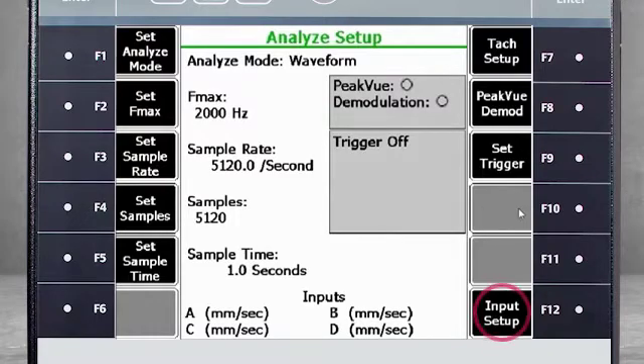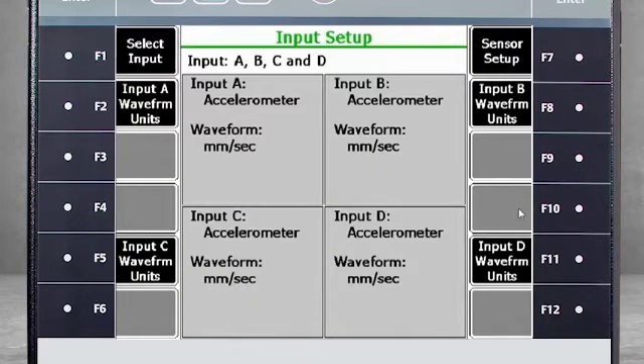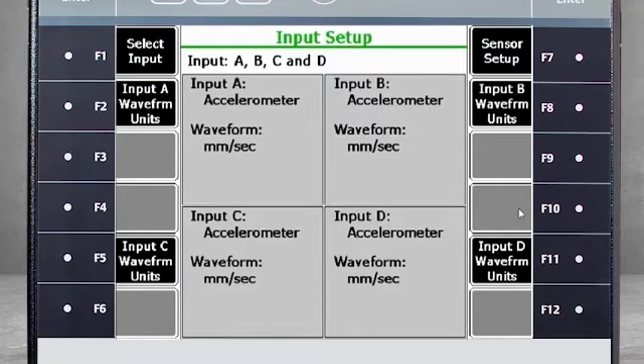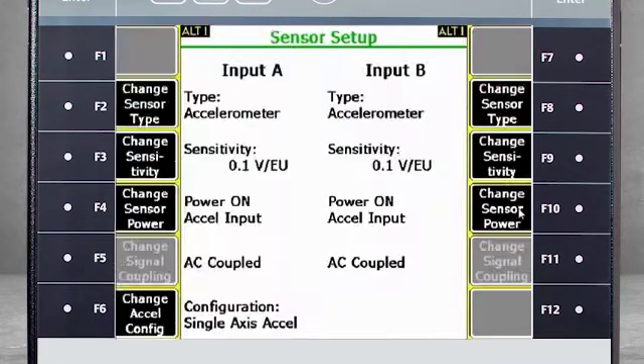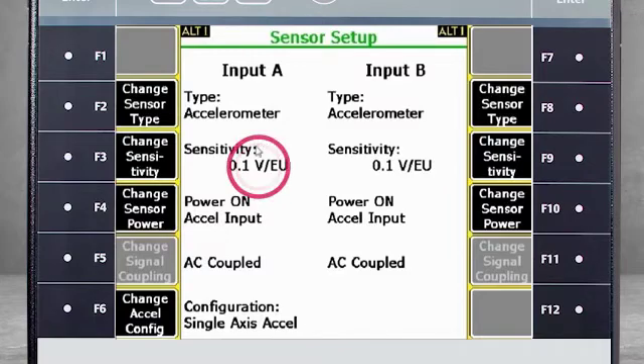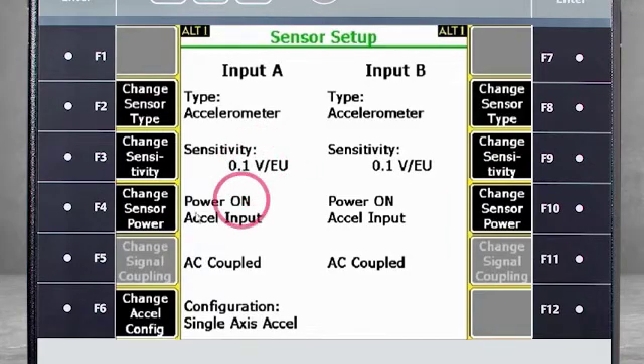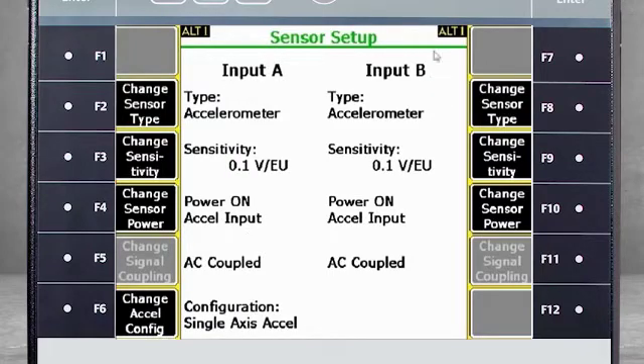Select F12 Input Setup to specify how many channels will be used simultaneously. We will use 4 channels, but you could use F1 Select Input to deactivate any channels if you wanted to use fewer. Use F7 Sensor Setup to define the kind of sensors you are using. In this example, we are using accelerometers with 100 millivolt per engineering unit and power on. This is a fairly standard setup on Input A, and we will use the same on Input B.